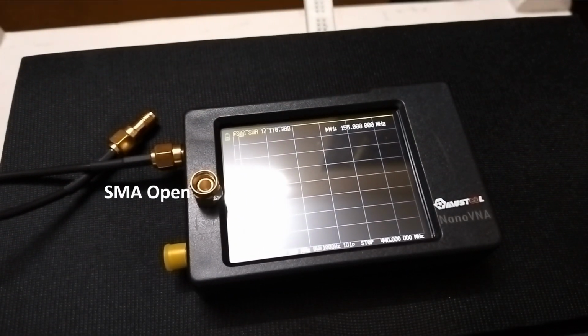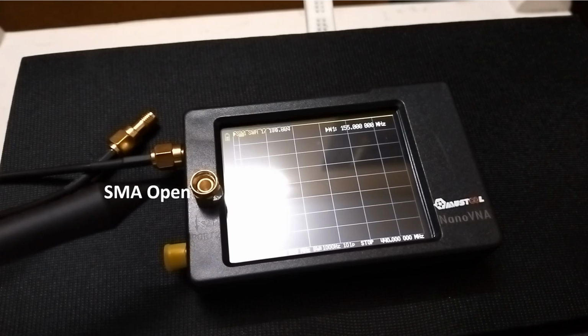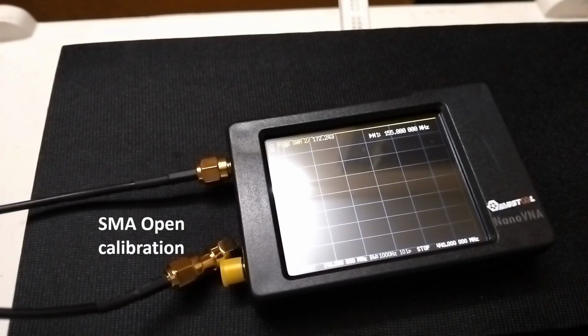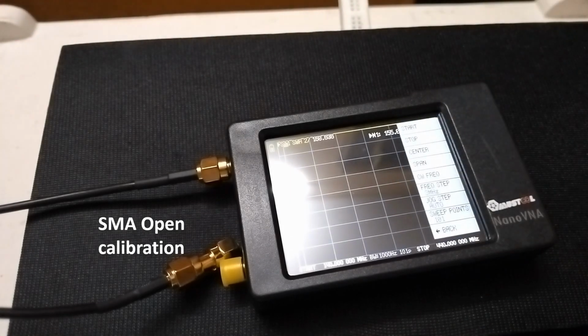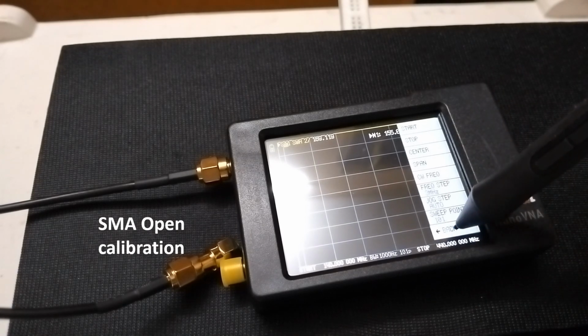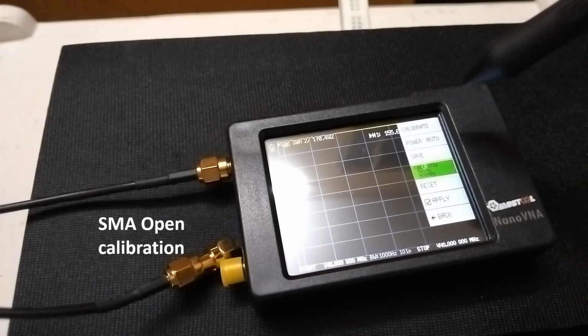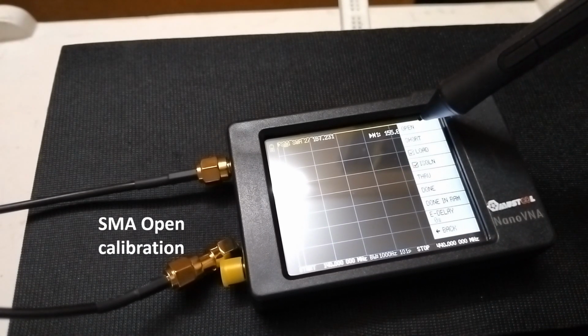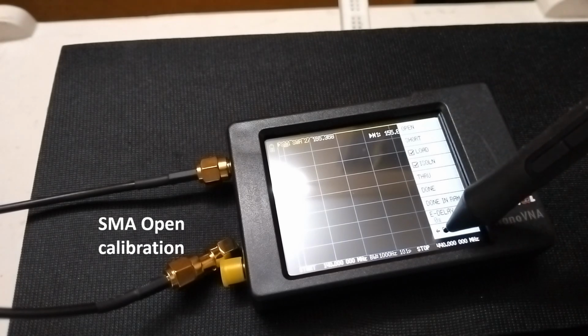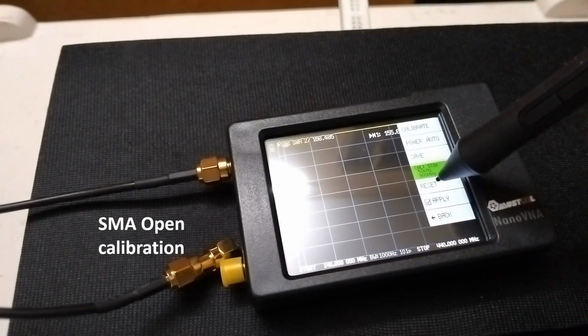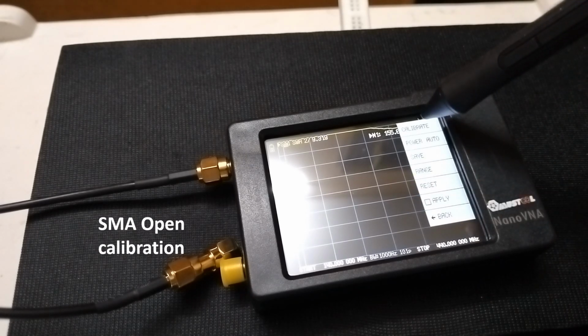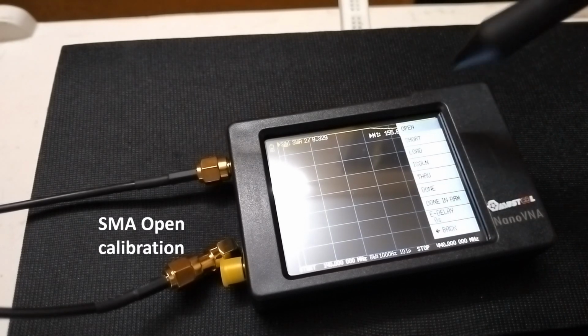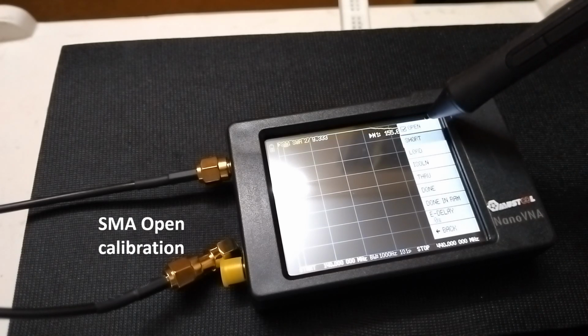Next I am going to connect this SMA open connector. The SMA open connector for calibration has been connected. Now I'll use calibrate, open. Before that I have to reset the calibration. Calibrate open. So the open calibration is done.